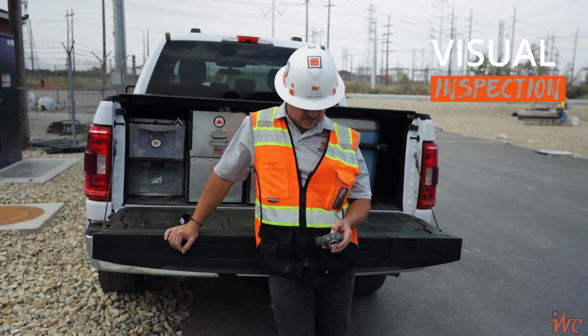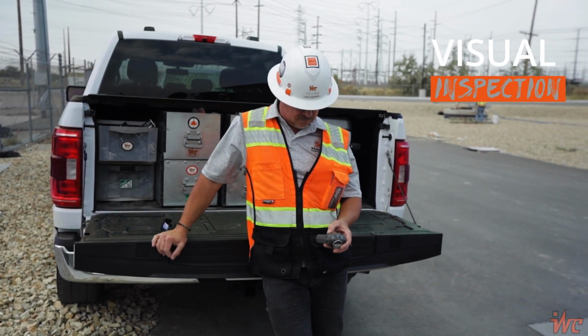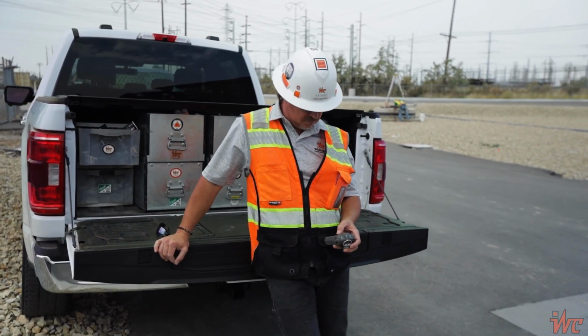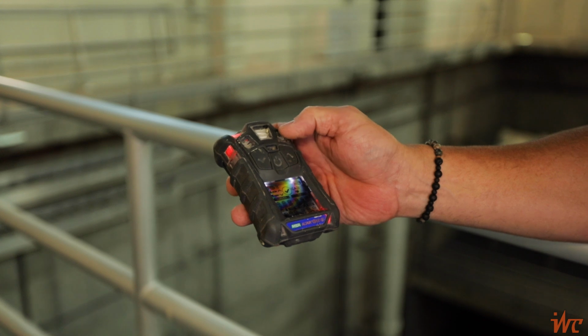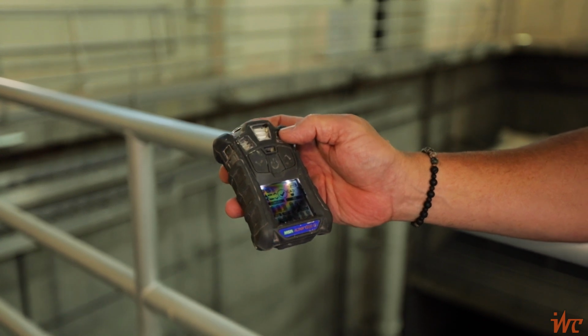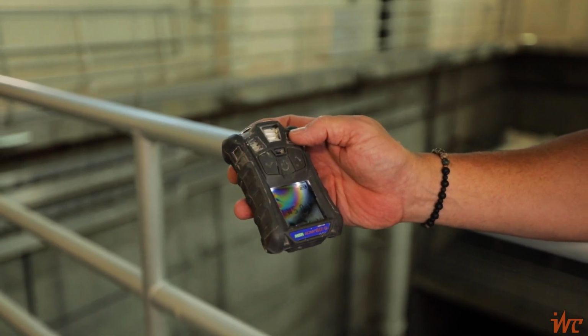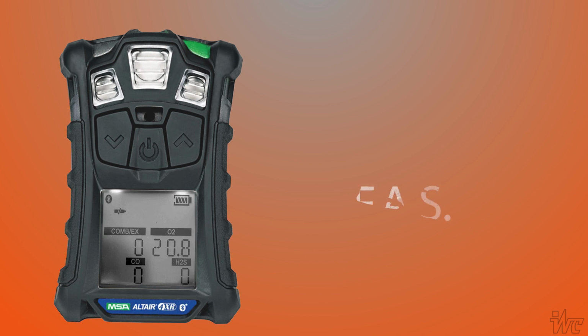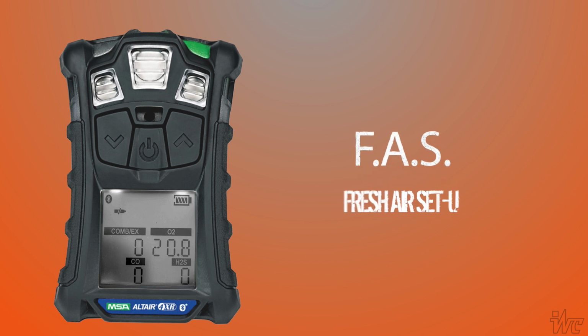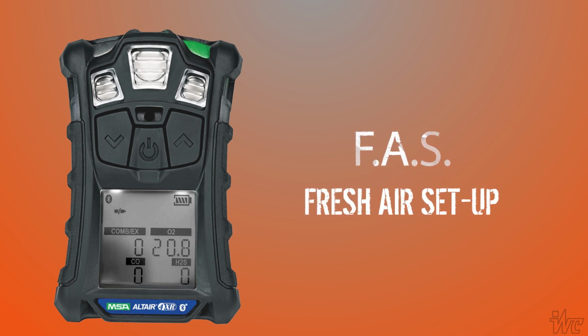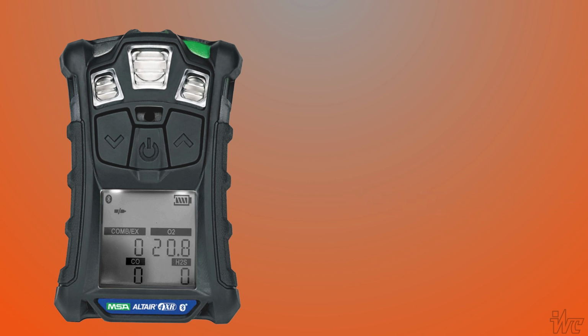First, do a visual inspection of the casing of the gas monitor to ensure there is no damage. Then, power on the gas monitor. Once the monitor is powered on and has gone through its self-tests, the letters FAS will start flashing on the screen. FAS stands for Fresh Air Setup. This test sets a baseline measurement for hazardous gases.